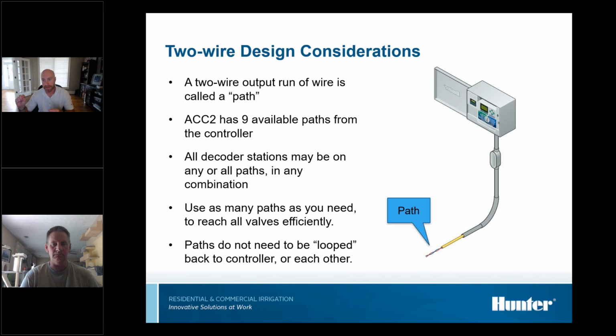That's what I mean. So you've got one pair of two wires leaving the clock going out to the field. That is what we call a path. The ACC2, which is this guy behind me here, the one on the slide is actually our original ACC1. The ACC2 has 9 available paths from the controller if you use all the expansion modules. With the base package, it has 3, but you can expand that up to 9. So you have 9 available, what we call two-wire paths from the controller.